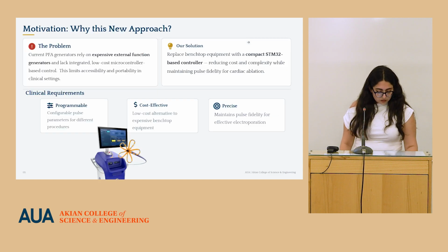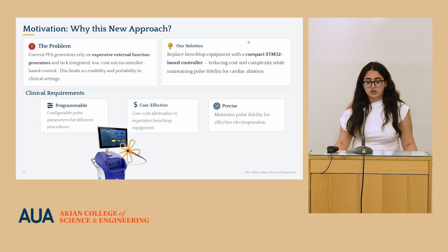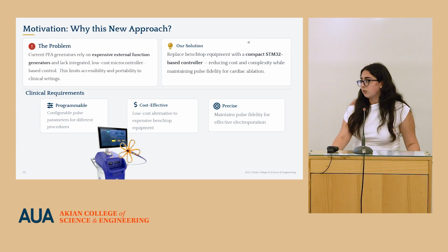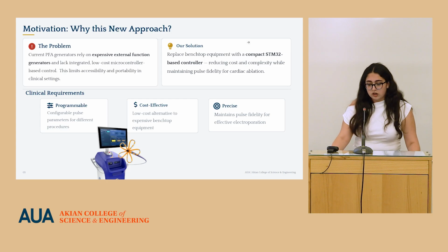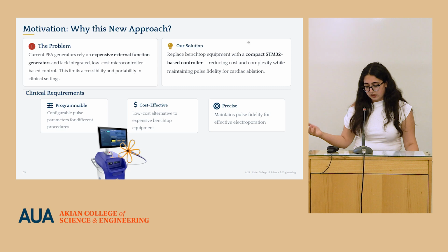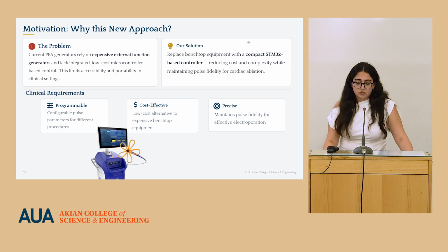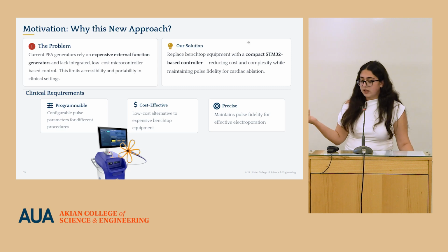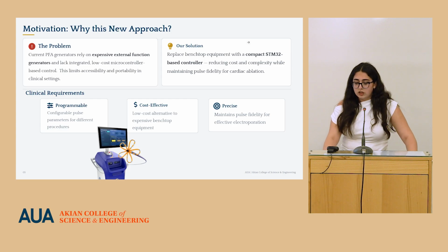So why are we working with this new approach? Current PFA generators rely on expensive external function generators, and they lack integrated low-cost microcontroller-based control, which is also why in Armenia, for example, we don't have that device yet in laboratories or hospitals. So our solution, with the device that Tigran and Wahab created, was to replace the benchtop equipment with a compact STM32-based controller.